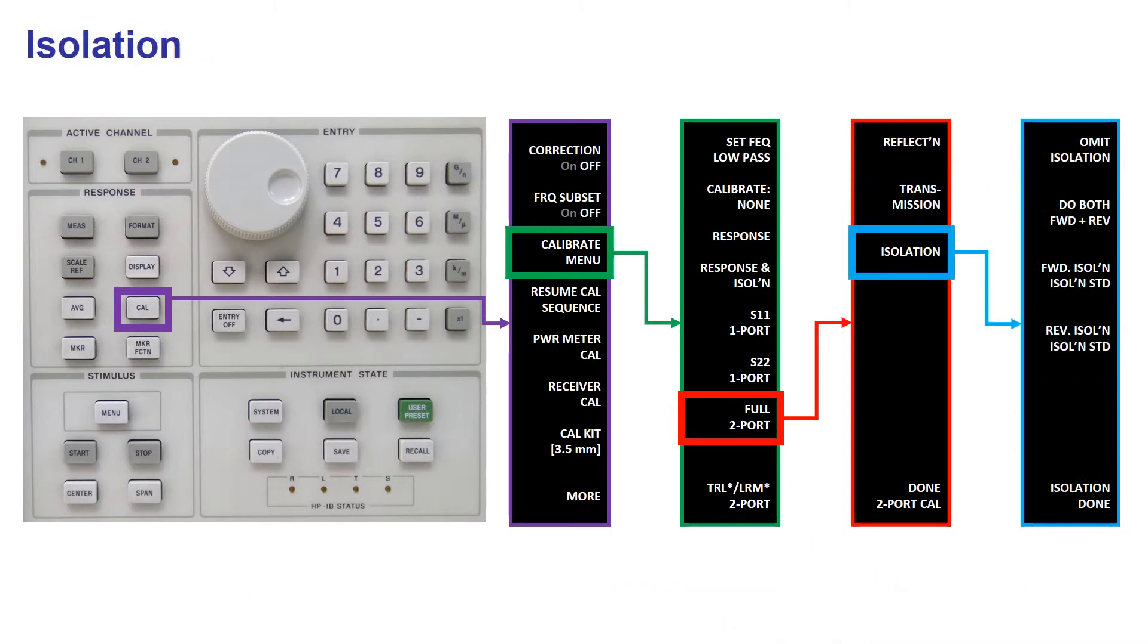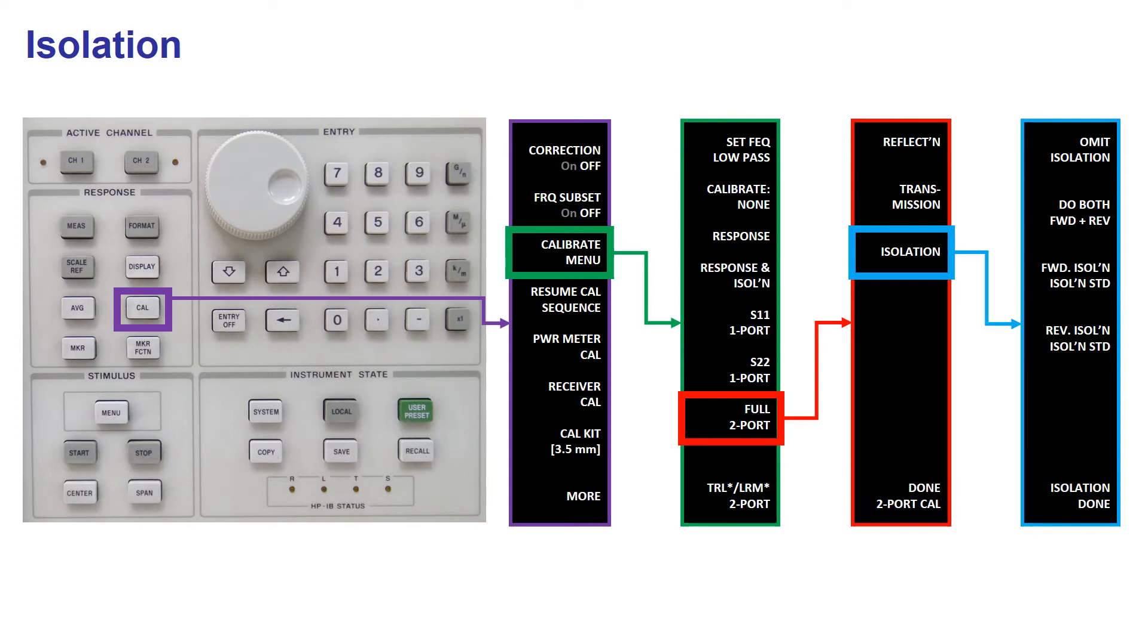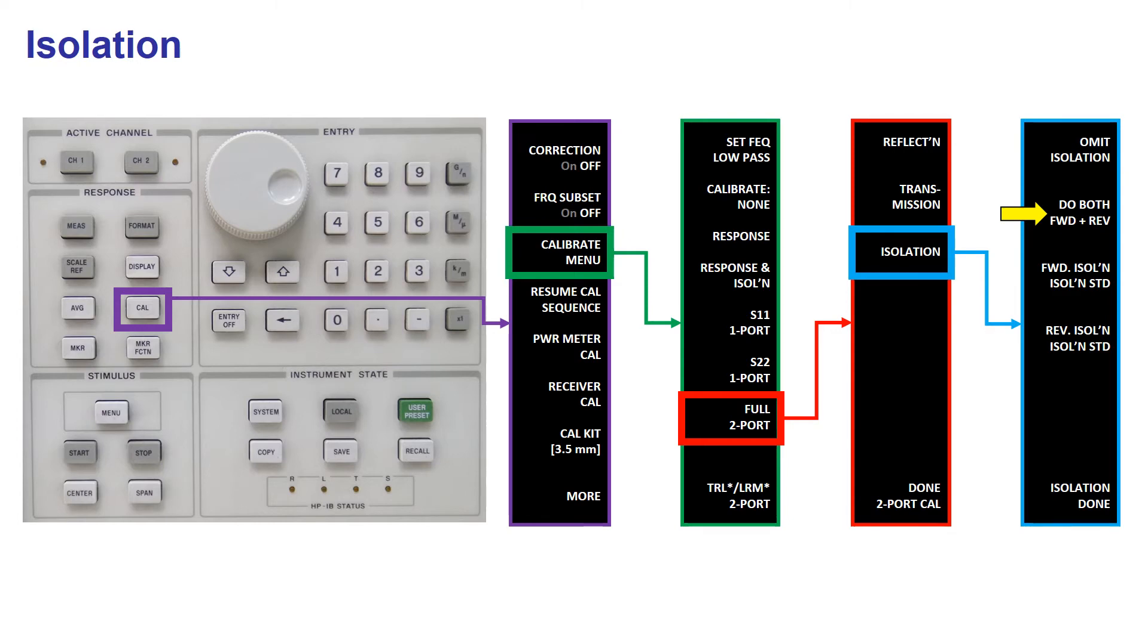In the last part of the calibration you do isolation measurements. These measurements need that you physically isolate ports 1 and 2, for instance by connecting matched loads to both ports. Then you press Do both forward and reverse. If you are not interested in wide dynamic ranges or very low transmission coefficients, you can skip this step by choosing Omit Isolation, nevertheless you don't save much time by doing this.